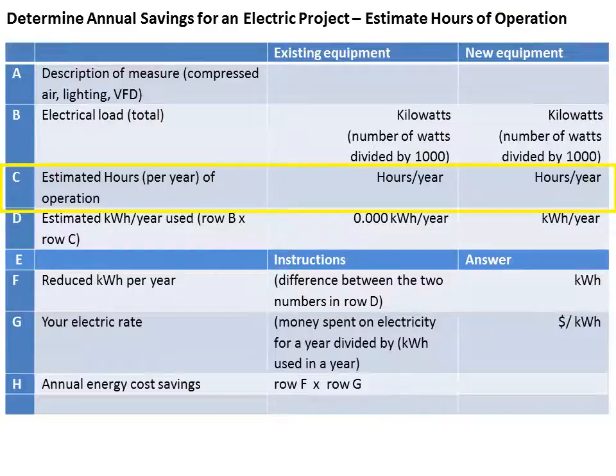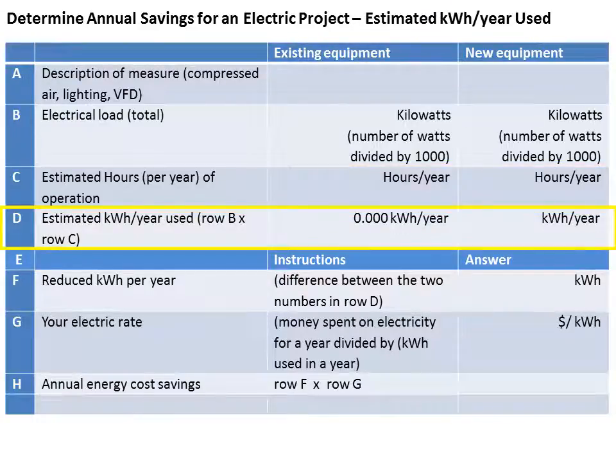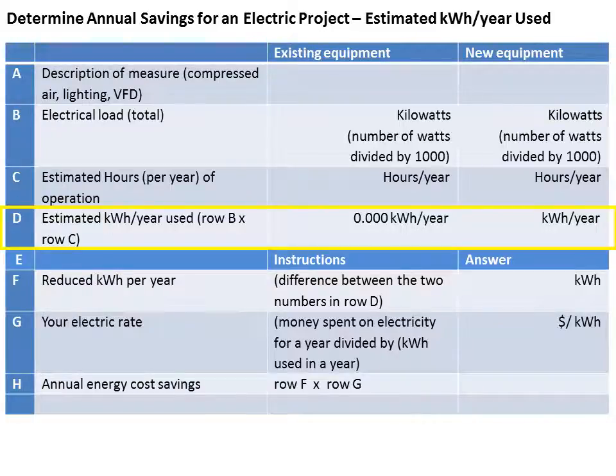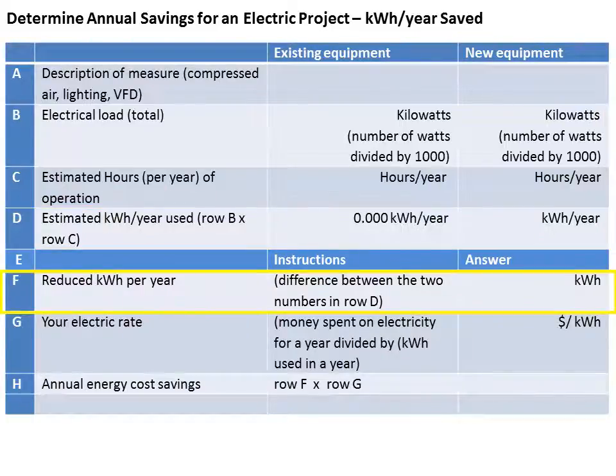Next, estimate the number of hours per year the existing equipment is being operated and the number of hours the new equipment will be operated. For example, your equipment may be used around the clock for six days every week, or you may only use it for eight hours per day five days per week. Then multiply the electrical load of the equipment in row B by the estimated hours of operation in row C. Do this for both the existing and new equipment to get the estimated kilowatt hours per year for each. Now determine your reduced kilowatt hours per year by figuring the difference between the numbers in row D.